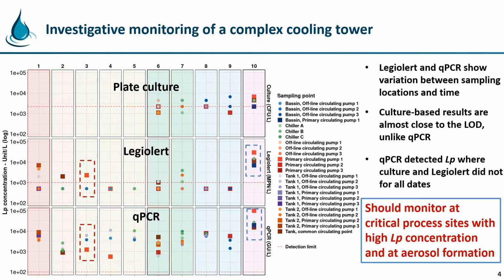In the second part of our study, we monitored L. pneumophila in a complex industrial plant using AFNOR plate culture, Legiolert, and Bio-Rad qPCR. Monitoring locations within the circuit included pumps, basin, tanks, and chiller, performed from April to July. Colored boxes indicate that water sampling was done during the same 40 minutes on the same days, and numbers show different sampling points. The red dotted lines show the detection limit of each method.